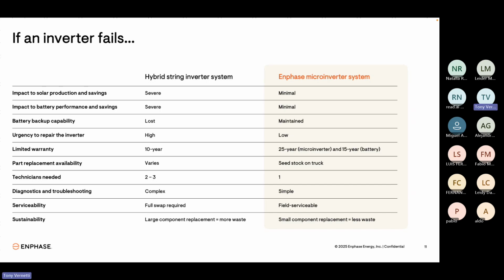If a hybrid inverter fails, the battery completely stops working. Whereas with Enphase, we have individual microinverters in our batteries as well. So the battery will still keep working. Backup power is going to be maintained if there's a failure in a microinverter system. Urgency to repair the inverter is much lower.